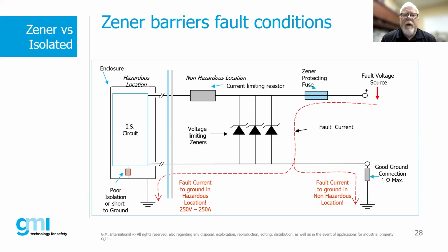Now, this is what could potentially happen in a Zener barrier fault condition. If we have a fault and we don't necessarily have good ground, or even if we do, we could potentially have that fault condition carry into the hazardous area. That's a potential issue where we might create a spark that could cause an explosion in a hazardous location. So if you notice, on our circuits, when we use intrinsic safety and Zener barriers, we have to have a good ground that is typically separate from what we would call our normal dirty earth. We might call it clean earth, we might call it IS earth. Many people call it different things, but we want to keep that separate from our normal dirty earth. And there are some things you have to do with regards to addressing that. But generally speaking, we want less than 1 ohm resistance between the Zener barrier, in this case, and our ground. And we want to keep that clean so we don't have any noise, feedback, fault conditions, or anything else coming up through the barrier on the backside.